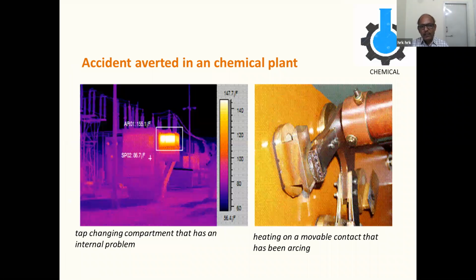Another case: we randomly checked a transformer. The OLTC cabinet temperature was very high. On checking, the OLTC moving contactor had got fused due to periodic movement and regular operations. That prevented the failure of the transformer.